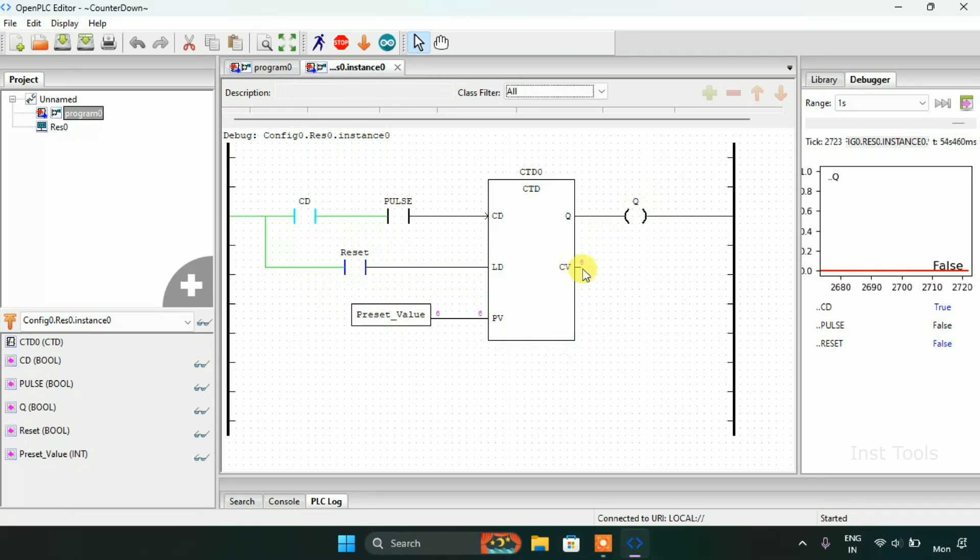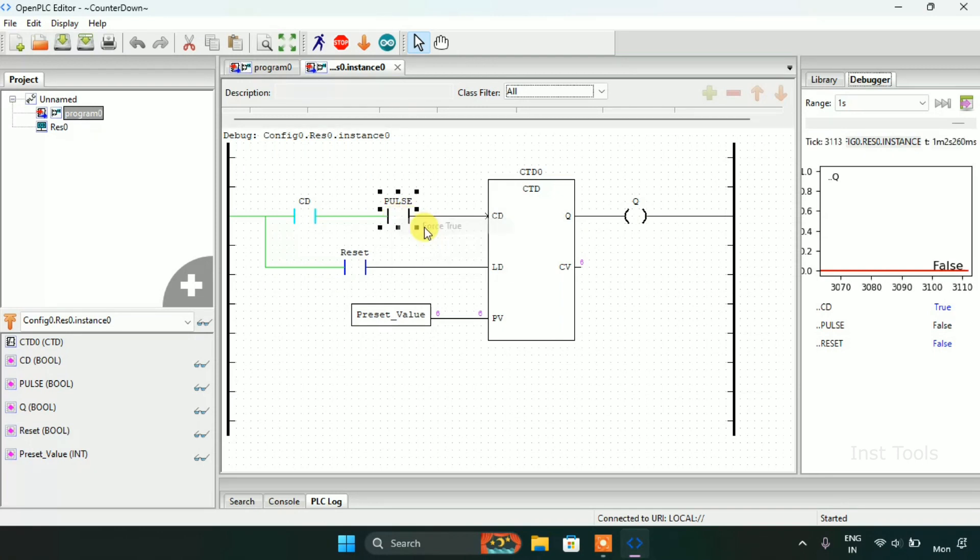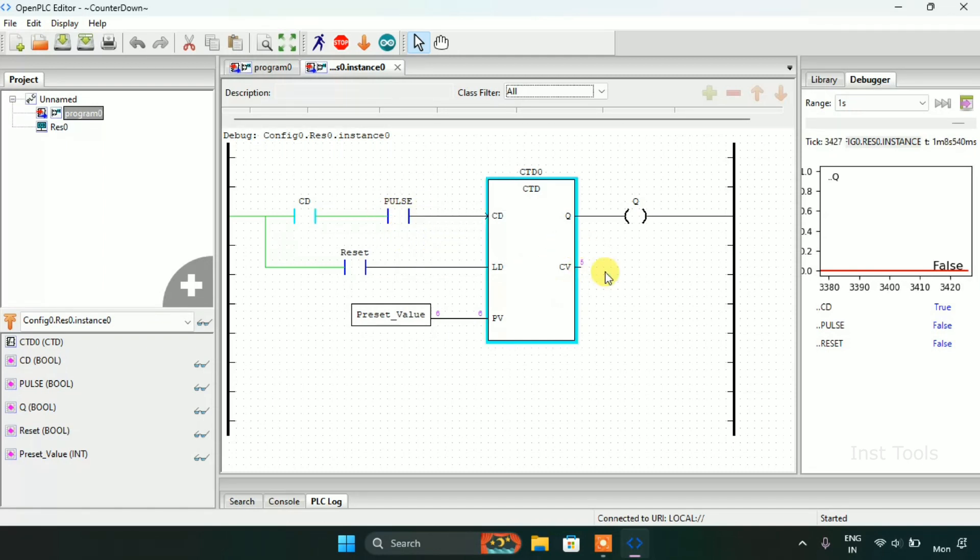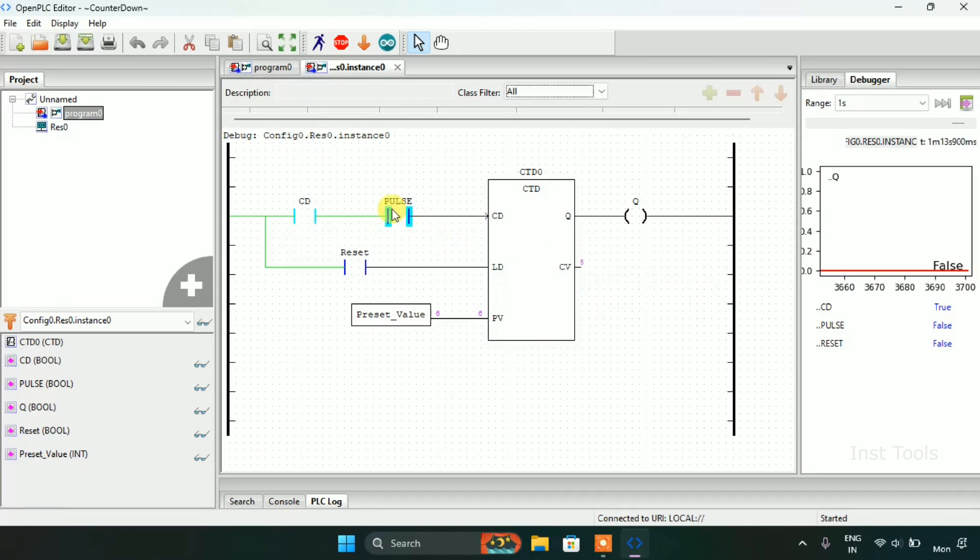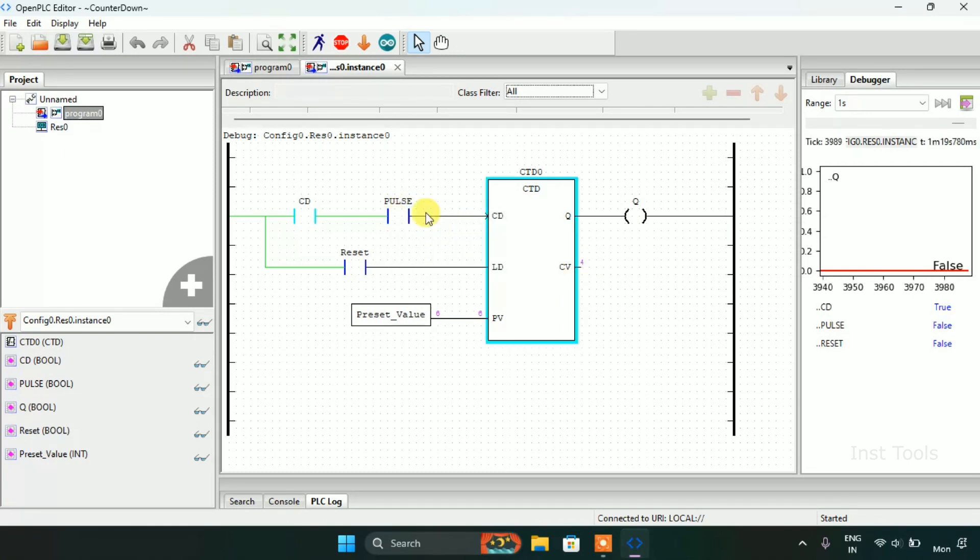Now again when I force it to false, the Q and CV is indicating the same values. I will start forcing the pulse to true and forcing the pulse to false. Now the CV starts counting down - first it was six and now it's five. Again when I force it to true and again it falls, the CV is four.